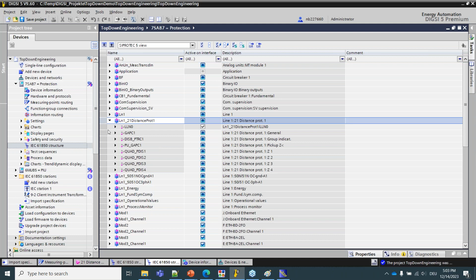As mentioned earlier, every device from the manufacturer comes with its default data model. Why? Because the 61850 standard standardizes logical nodes, but it doesn't standardize the structure with logical devices, or the prefix and suffix names used in the protection functions. So here, for a distance protection device from the Siemens SIPROTEC 5 family, by default it's modeled with a logical device called LN1 distance prot, containing a certain number of zones by default.